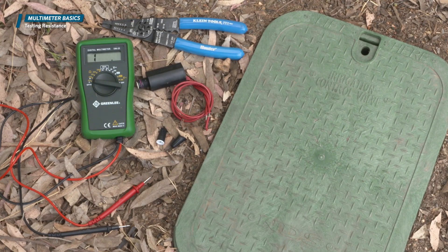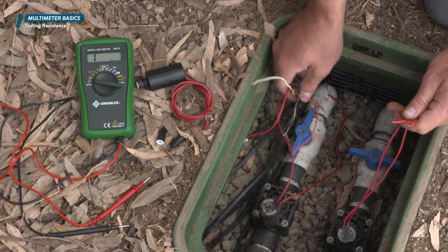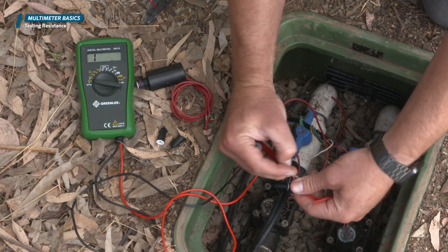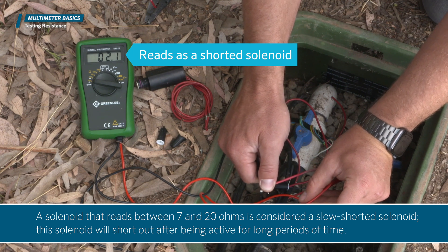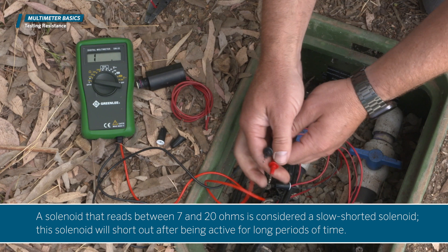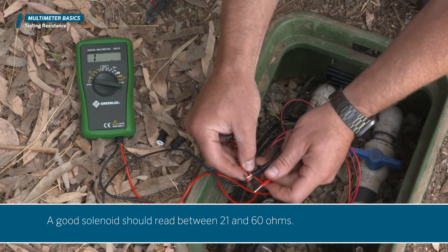Now you can go to your valve box and test just the solenoid. Resistance is measured in ohms, so the multimeter needs to be set to ohms. To test the resistance on a solenoid, the solenoid needs to be disconnected from the wire. Touch each of the probes to each of the solenoid leads — the order does not matter on AC solenoids. A shorted solenoid will read between 0 and 10 ohms. A solenoid that reads between 7 and 20 ohms is considered a slow shorted solenoid, which will short out after being active for long periods of time. As a rule of thumb, any solenoid with resistance of less than 20 ohms is considered a shorted solenoid. A good solenoid should read between 21 and 60 ohms.